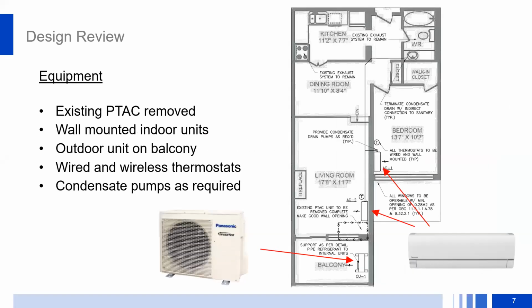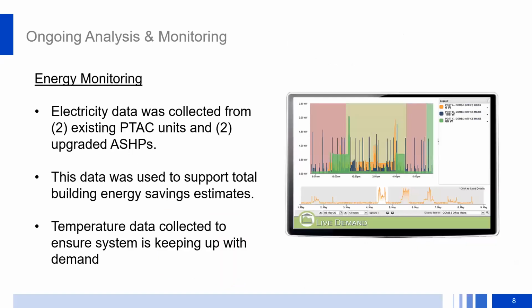A closer look into the design review details: the existing PTAC was located at the bottom of the floor plan between the living room and balcony, so it would be removed. The outdoor unit would sit on the balcony, and the indoor units would go along the interior wall through the middle of the floor plan. We'd have wired and wireless thermostats available, and for condensation concerns, if the condensate line couldn't be gravity fed, then condensate pumps would be installed within those indoor units wherever required. Next slide.